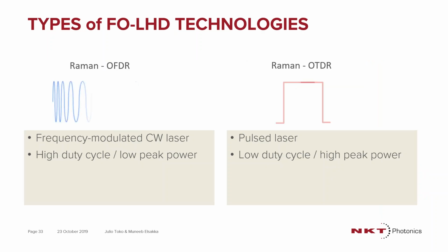There are two different types of technologies, depending on what vendor you're going to use. There is Raman OFDR, and there is also Raman OTDR. They both have their advantages and disadvantages, but both of them do the same thing. It's giving you distributed temperature sensing all across. So in the case of OFDR, the light is constantly on, but you're actually just sweeping the wavelength a little bit. In the case of OTDR, it's a laser pulse. Imagine turning the light on and off. So that's the type of light that's traveling within the fiber.